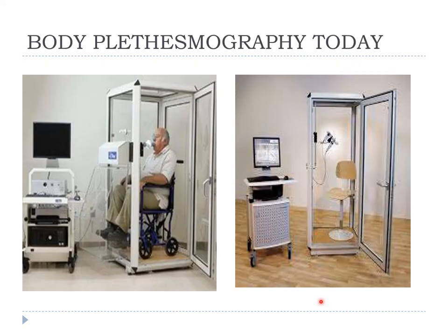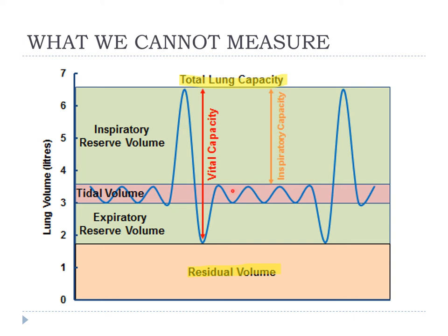So I will be explaining everything in detail. This is a body plethysmograph. There is a computer attached which helps in the calculation of the airway resistance as well as the lung volumes.